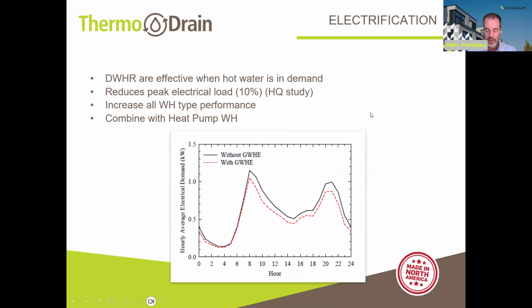Electrification is a subject that we're talking about a lot these days. And so there was a study done a few years back where it showed that essentially drain water heat recovery was able to reduce the peak electrical load demand by about 10%. Obviously, some of your high energy loads is heating hot water. In the morning and in the evening when people are showering, that's when you're also doing your cooking and maybe some cleaning and so forth. So that's where the highest electrical load is. And as I mentioned earlier, the thermodrain unit is reintroducing a lot of energy into the system, so it reduces the hot water heating load significantly. And this is what it does for the grid.